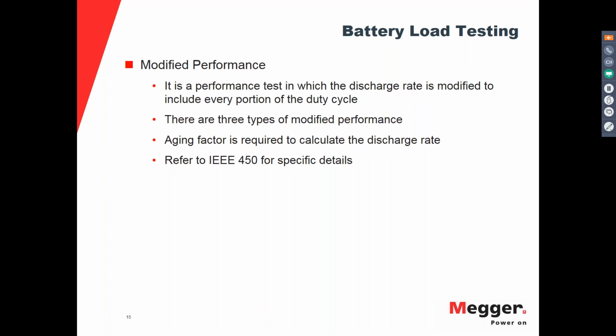And then the modified performance test is a test that can do both. It will do the profile, and then once the profile section, or the duty cycle section, of the test has finished, the test is continued with a constant current as from the manufacturer's tables, and then you get the capacity. So you are verifying both aspects: the duty cycle, and you're getting the capacity value of the battery. This test is a little bit more complicated than the other ones, and you need to include aging factors in the calculation of the discharge rate. And well, I suggest that you refer to IEEE 450 for specific details for these.